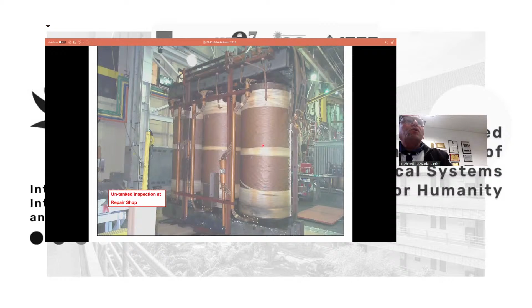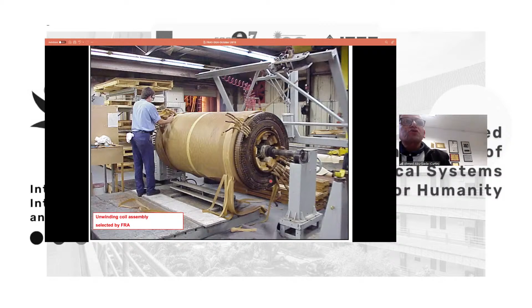But when you look at another signature, this one here, even if you don't have any experience with frequency response analysis, you will observe that one of them is significantly deviated from the others in the low frequency range, which means that this transformer has something wrong in this phase. So what we have to do is take the transformer out of service and unwrap the winding. The suspected winding was this one here, so we have to take it to the workshop and take the papers out, unwrap it.